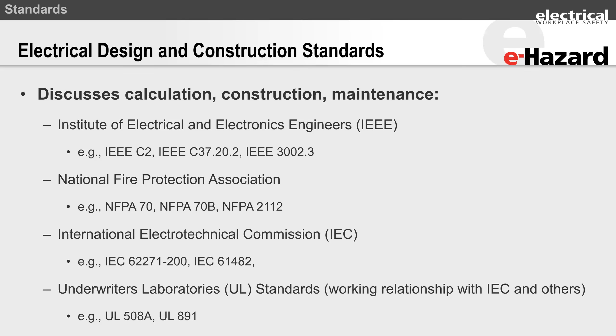Then you have the UL standards, which also have a close working relationship with IEC and other standards organizations. You've got 508A that speaks about control panels, and UL 891, an all-encompassing standard with regards to switchgear assembly. So you can see that although these are called electrical safety standards, they're not really focusing on work practice. When we talk about work practices, the standards become very narrowed, because they aren't that wide of a net of standards talking about switchgear, transformers, motor control centers, panel boards, control panels, etc.